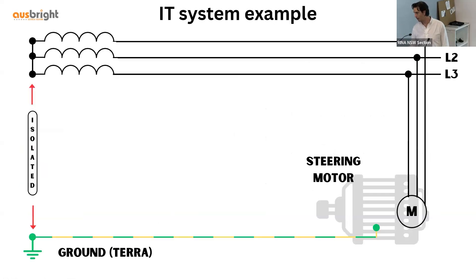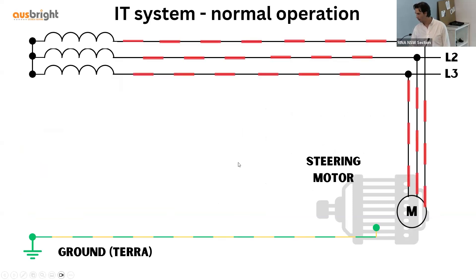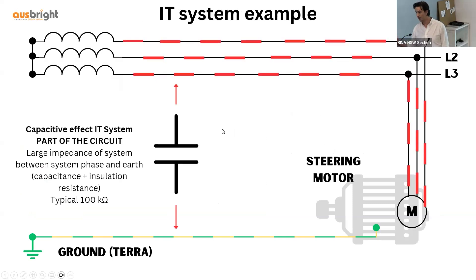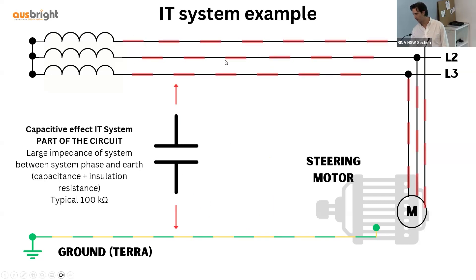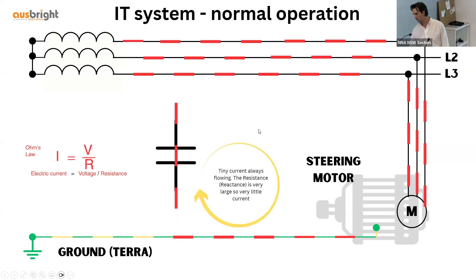Stepping through an IT system example, here we have a steering motor isolated from ground as you would find on a vessel. In normal operation, currents are flowing with no problems. One important thing to remember with IT systems is the capacitive effect — there is current continually flowing through the capacitor and insulation resistance. It is a very large resistance, unlike your cables, so always there is a tiny current flowing. Very large resistance, very small current.